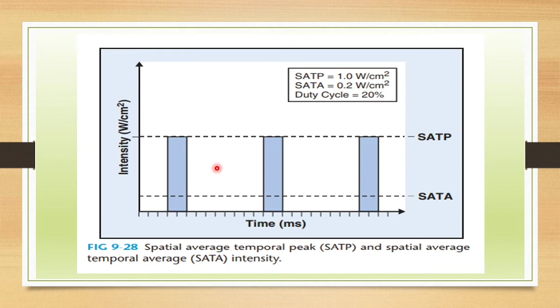So spatial average temporal peak intensity multiplied by duty cycle is equal to spatial average temporal average intensity. For example, if the spatial average temporal peak intensity is 1 watt per centimeter square, with a duty cycle of 20% in pulsed ultrasound mode, then 1 into 0.2, the spatial average temporal average intensity will be 0.2 watts per centimeter square.